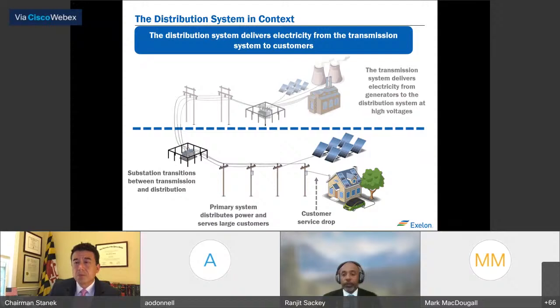This slide shows an overview of the power grid that enables electricity to be delivered to and from customers. As the commissioner said at the beginning, above the line we have the transmission grid, usually above 69,000 volts, where bulk power is generated, transmitted, and delivered to the distribution system. Below the line is the distribution system, which is what we'll focus on today because it's what we're working on and what's regulated at the state level. The distribution system is typically made up of medium voltage or primary components, from 4,000 volts up to 69,000 volts in some areas, and low voltage or secondary components typically under 600 volts. We'll talk about distribution substations, the primary system, and the secondary system in the next few slides.